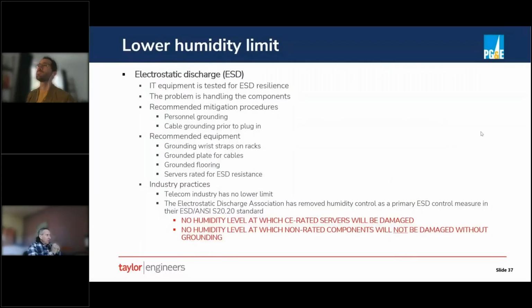Besides temperature and humidity, there are other environmental criteria that are of interest and concern in data centers. Well, actually, this is still on the humidity side. So where does the lower humidity limit come from? The ASHRAE lower humidity limit has changed over the years. It used to be 20% or 30% lower humidity. Now it's 8%, but it also has a minimum dew point. And the concern with the lower end, the explanation has typically been electrostatic discharge.